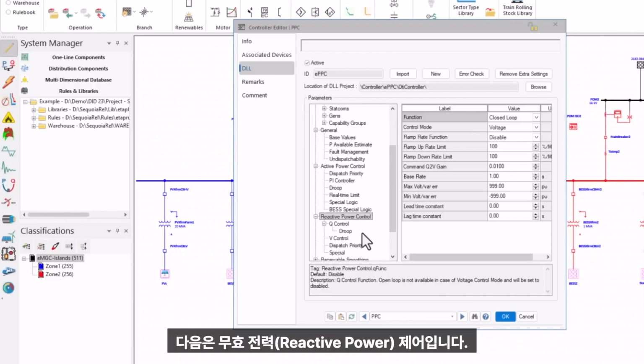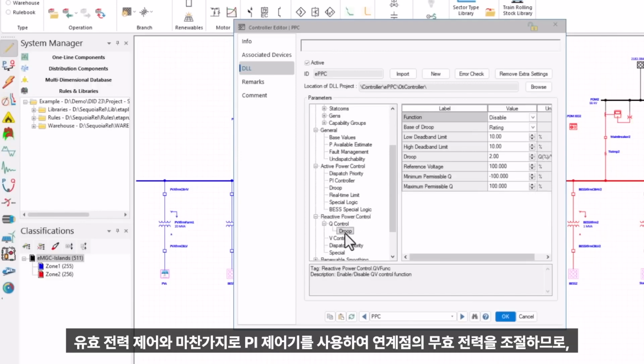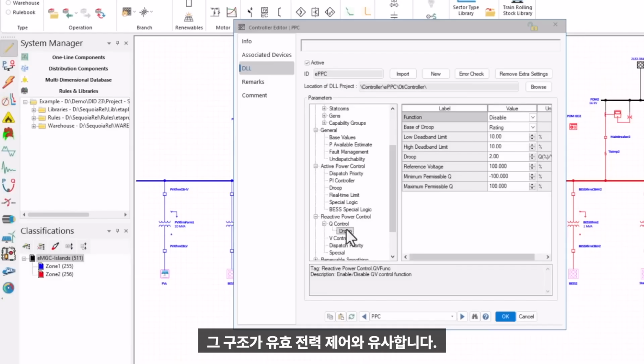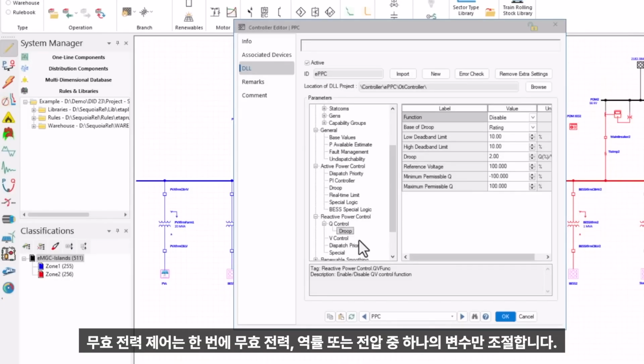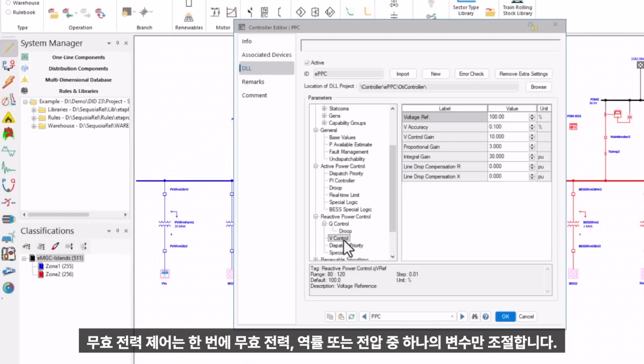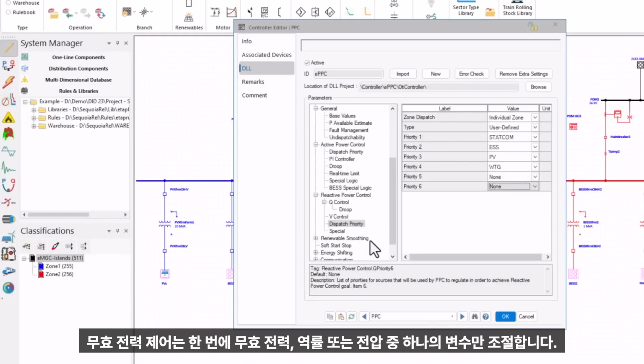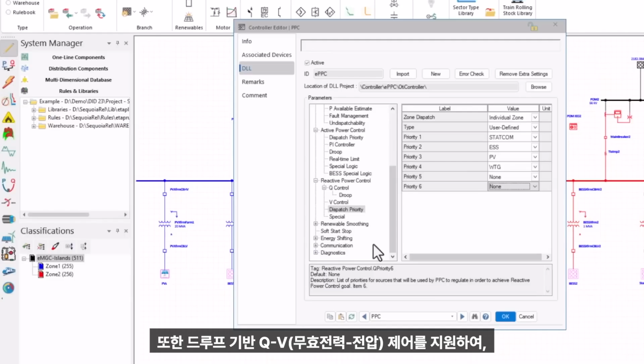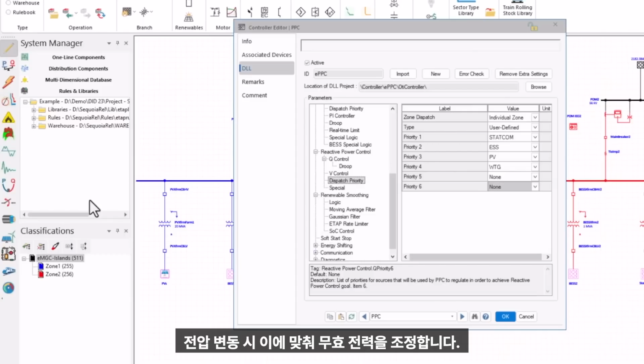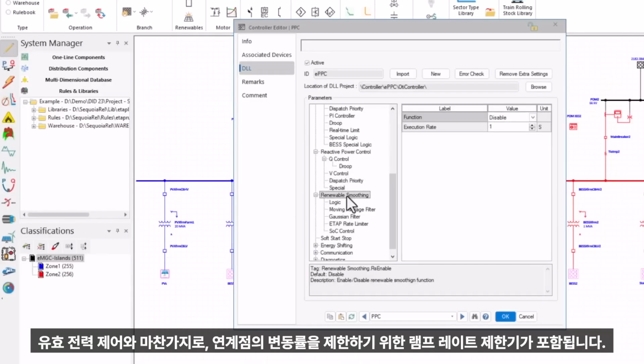Next, we have reactive power control, which is similar in structure to active power control because it also uses a PI controller to regulate reactive power at the point of interconnection. Reactive power control regulates one of three variables at a time: reactive power, power factor, or voltage. It also supports a droop-based Q-V scheme which adjusts reactive power in response to voltage fluctuations. Like active power control, it includes a ramp rate limiter to limit the rate of change at the point of interconnection.